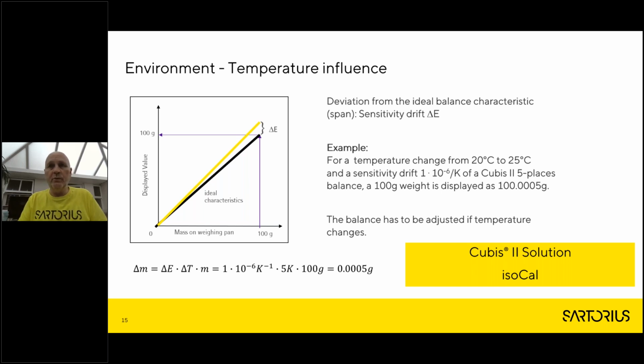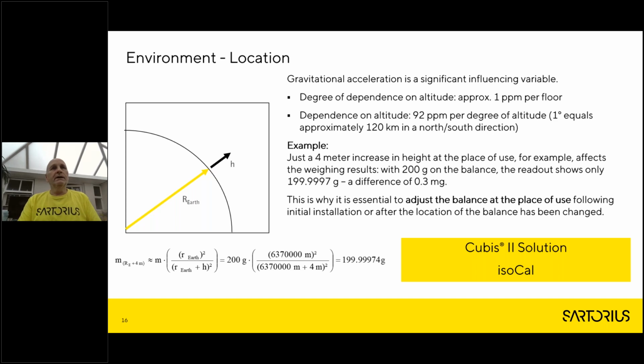So our solution on this would be the internal calibration, in our case, ISOCAL. Let's think of the location of the laboratory and the gravitational acceleration, which is a significant influencing variable. If you think about it, the higher up you are in, let's say, a 10-story or 20-story block of flats, the less is going to be the gravitational effect. So what we're saying here is wherever your balance is located, that's where it must be calibrated. If you use traceable masses, then you will be able to be confident that wherever your balance is, on the ground floor or on a higher floor, your balance will have the correct slope on it to be able to give you confidence in your results.